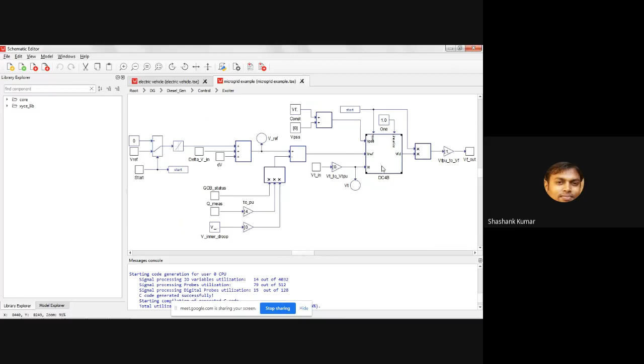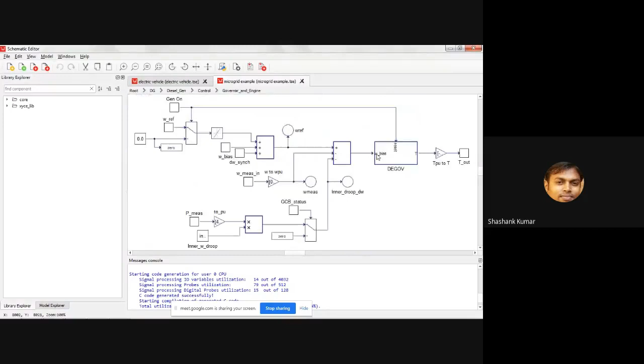If you want to see the look under mask, you just go through the block, and here you will find this is the generator, this is the measurement code, and this MCB and grid measurement block. In control, you will find the logics are developed like power factor control, then exciter start and stop switch. Then here you will find the exciter. A DC4B exciter is used. Then next, governor and engine parameters.